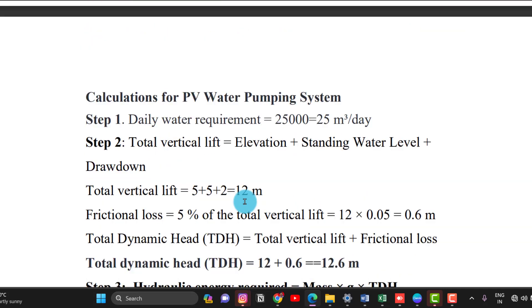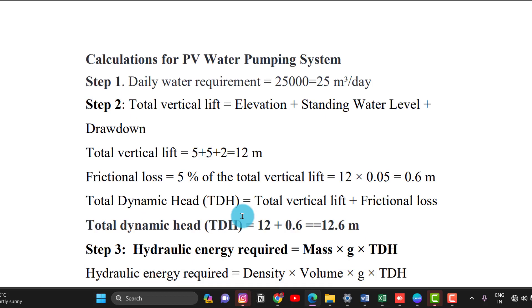Step 1: Water requirement is 25,000 litres = 25 m³ per day. Step 2: Total vertical lift is given as 12 meters. Friction loss is 5% of 12 meters = 0.6 meters. Therefore, total dynamic head (TDH) equals 12 + 0.6 = 12.6 meters.